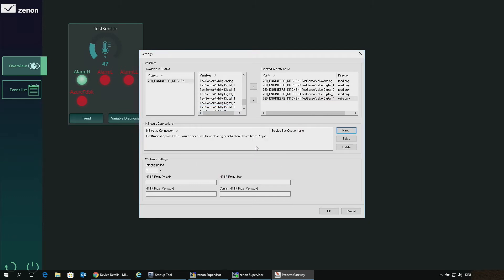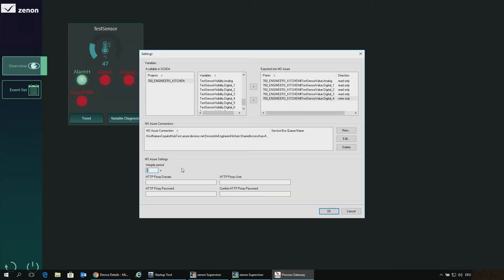You could also enter other connection strings if you want to send to a different device or to the Service Bus — that would also be possible. One more setting worth explaining is the integrity period. The integrity period means that at least every five seconds all the variables are sent to the IoT Hub, but they will also be transferred whenever a value changes — so it works in a spontaneous way as well.